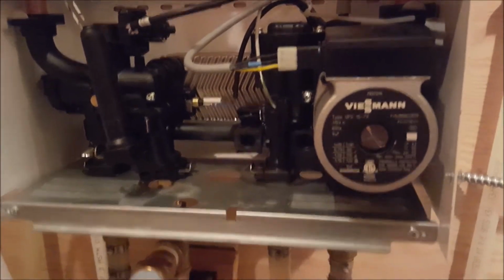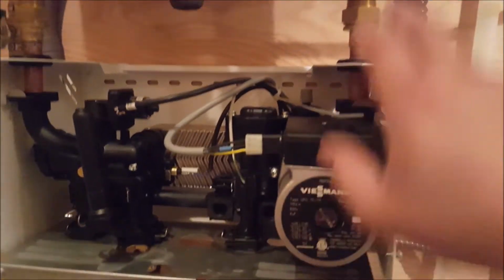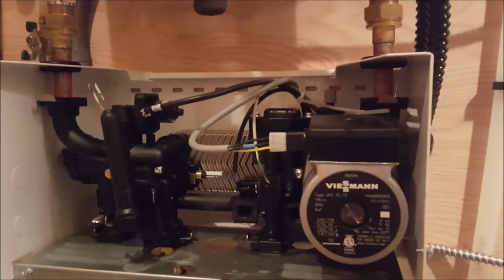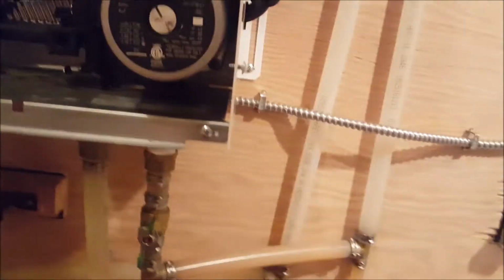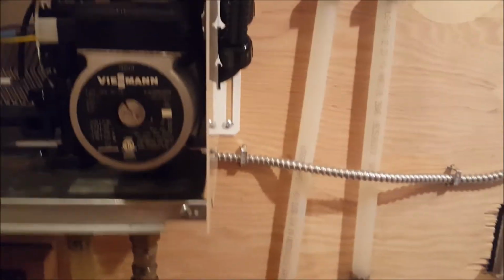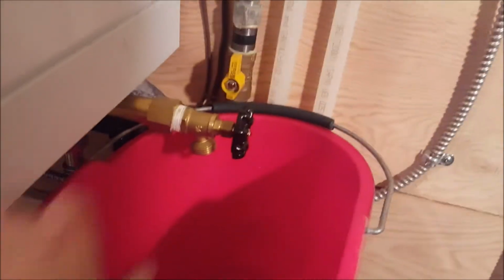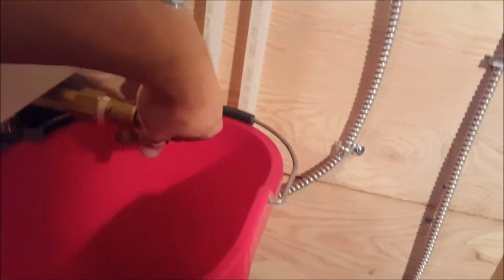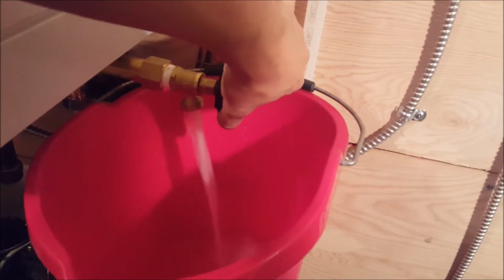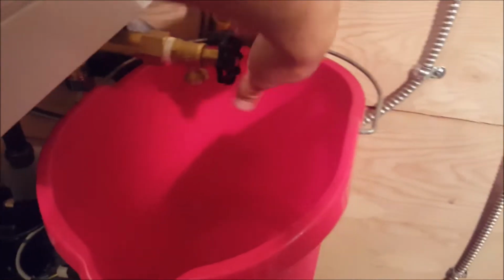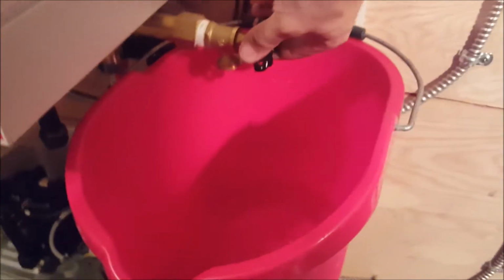Carefully, and look for leaks. You should see no leaks around the pump area, and you should see a little water coming through the pump into the heat exchanger. The best thing to do is crack this one open here for just a moment.